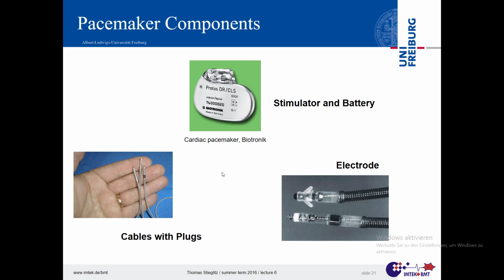For younger persons, they look like fishing rods made of silicone rubber, and we have the contact here at the tip. Most of those electrodes have just one contact at the tip. That's a beauty for the engineer, because you just need one cable with one lead. And it doesn't matter if there's a short circuit between one turn and the other, because it's just one lead, one cable. If you would have two, then they have to be both coiled in parallel, and they should be insulated and stuff like that. And you quite often take the backside of that IPG as ground electrode. So in the heart versus ground.